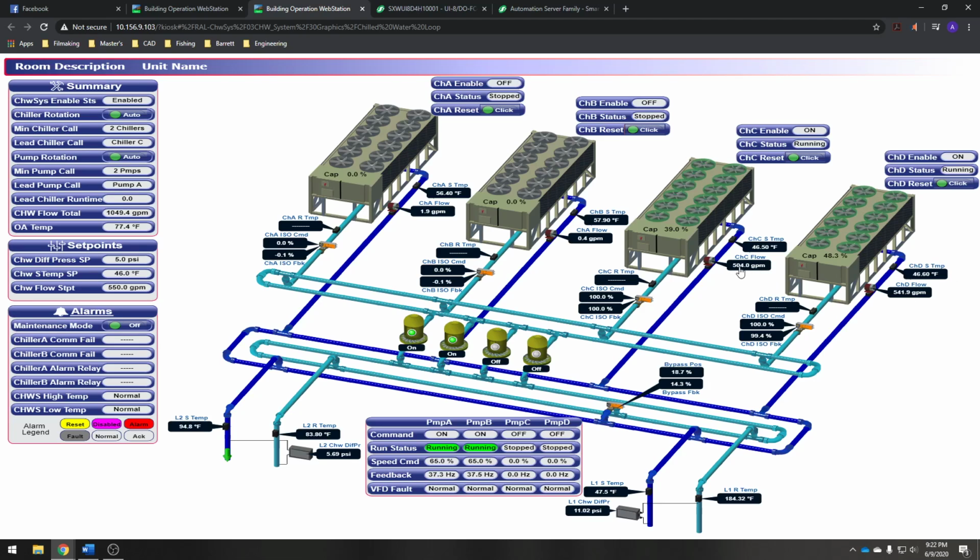So we're actually going to see it start modulating. This is at 502. It just commanded, and see it went to 20 from 17. Now it's saying, uh-oh, I've got to open more. And now we're seeing the flow increase. Once it gets to that set point, it'll evaluate and say, okay, now I'm at 600 GPM, let's back down. There it was, 25. It went from 27 to 25. Now it's going to 23, 22. That's exactly what the system's doing. This bypass valve, all it cares about is maintaining minimum flow over these chillers, which is 550, what we've told the system to do.